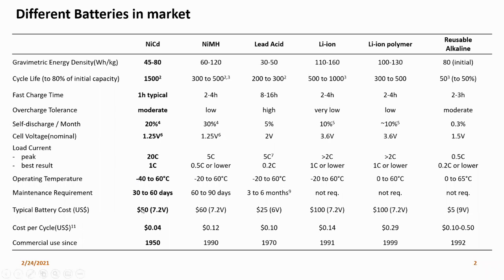One difference is the cost; it is slightly higher in nickel cadmium, but overall, as a battery bank, the operation cost or cost per cycle or replacement of battery is better, since nickel cadmium can operate for more cycle life than the lead acid battery. So overall, in 20 FEC, we may need to replace lead acid thrice, but nickel cadmium maybe twice. And if we operate the nickel cadmium battery per manufacturer specification, at the specific charge and discharge rate, I hope nickel cadmium has a much bigger advantage than the lead acid battery.